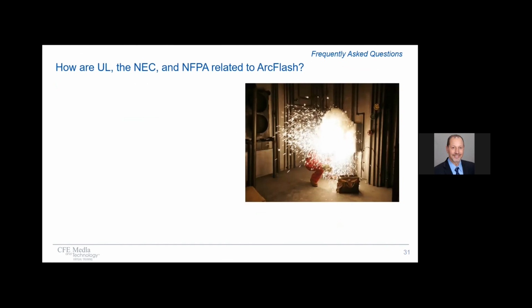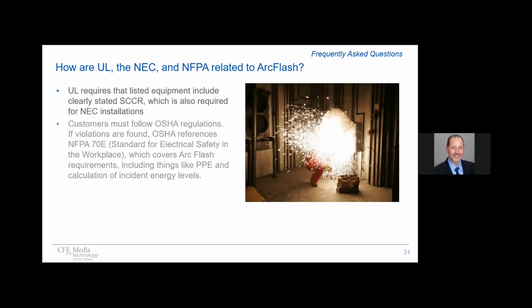Next question. How are UL, the National Electric Code, and the National Fire Protection Association related to arc flash? Well, UL requires that listed equipment include clearly stated withstand capability, or SCCR, which is also required for NEC installations. And customers must follow OSHA regulations, but if violations are found, OSHA references NFPA 70E, which covers arc flash requirements, including things like personal protective equipment and calculation of incident energy levels.